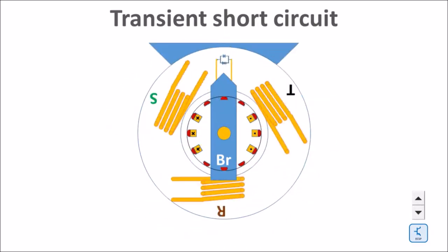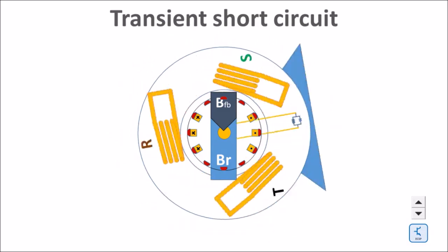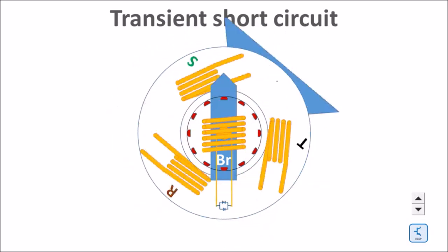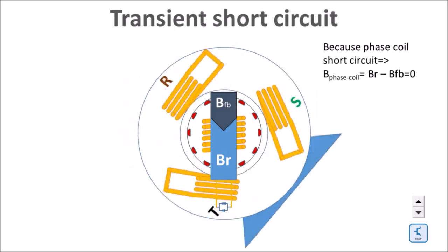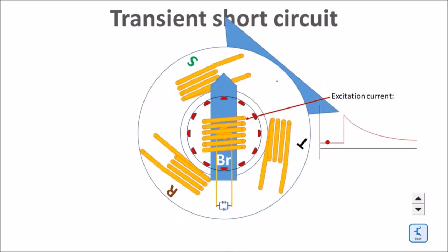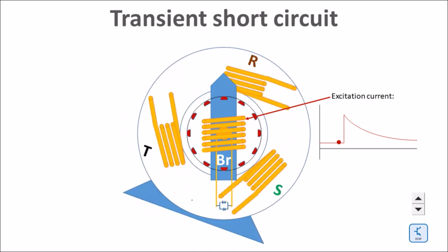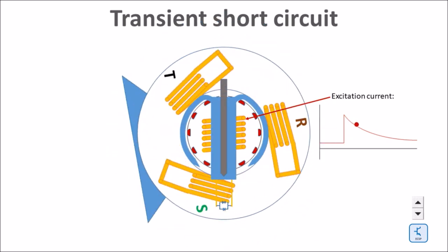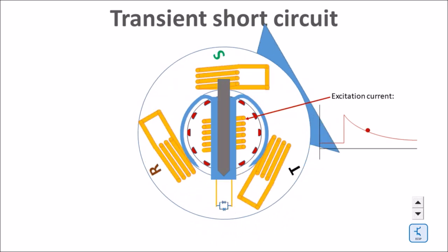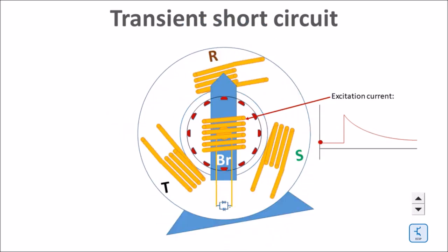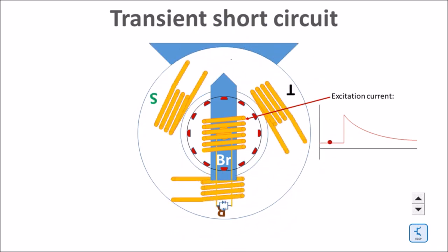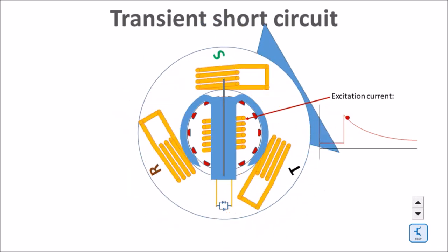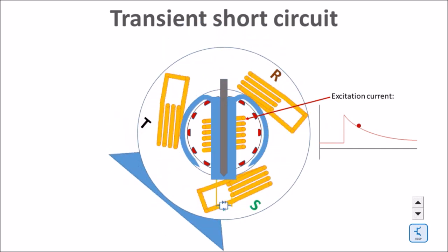Now you can look at the short circuit from the rotor's perspective. We replace the distributed stator coil by a long coil. We slow down the rotation a bit. Now you will see the effect of the three-phase short circuit. It produces a counter field to the excitation coil, the DC coil, which forces the excitation field to choose a path along the air gap of the generator instead of through the three coils of the three phases.